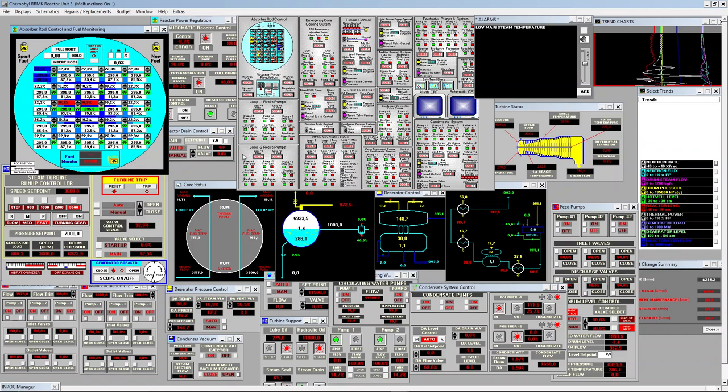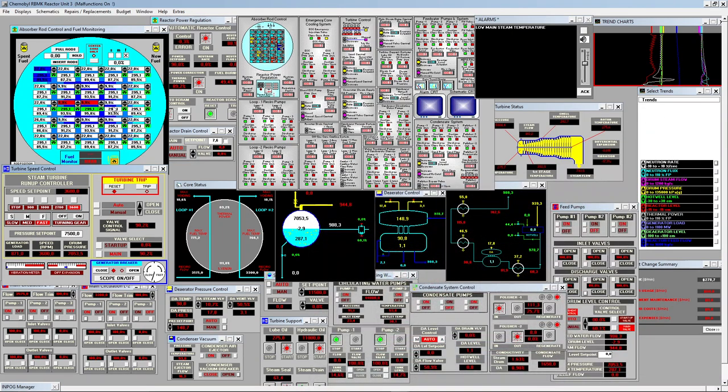Low main steam temperature. Maybe the refueling is blocked when you have low steam temperature. Let's increase it to 75. 75. Okay. Let me check, it's still recording, yes. Let's be careful with pressure set point changes. Change no more than 500 kilopascal at once, because very big changes in steam flow to the turbine could cause the turbine to vibrate because of differential temperature deformations. Okay, let's see if I can refuel now.